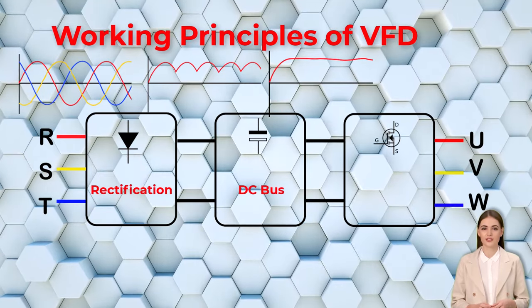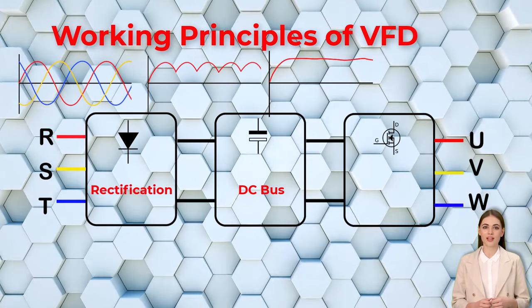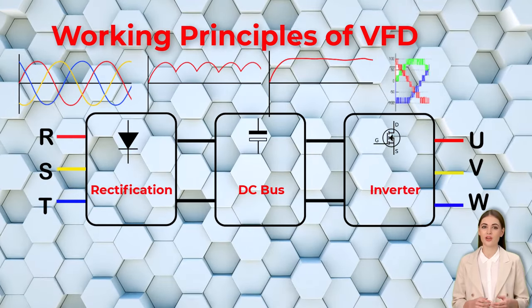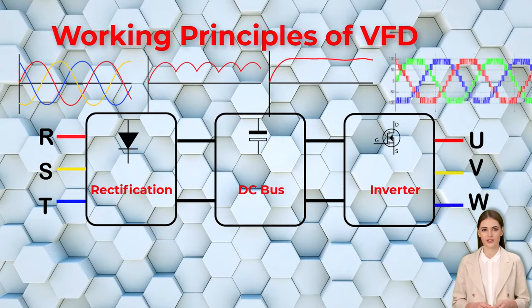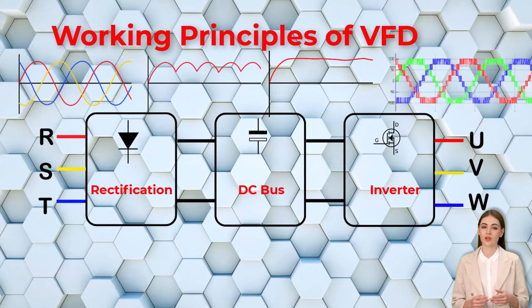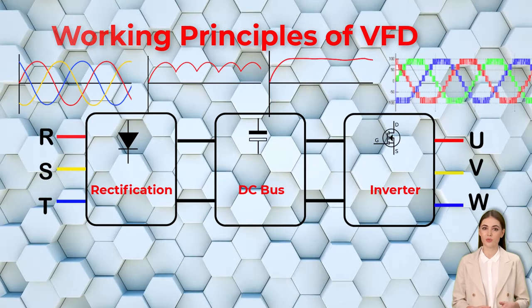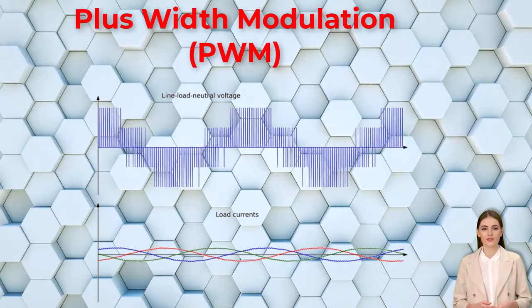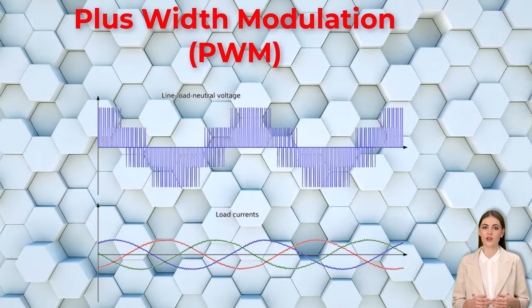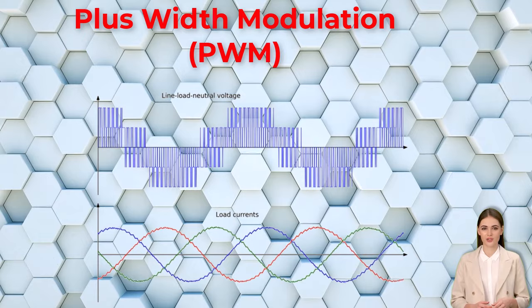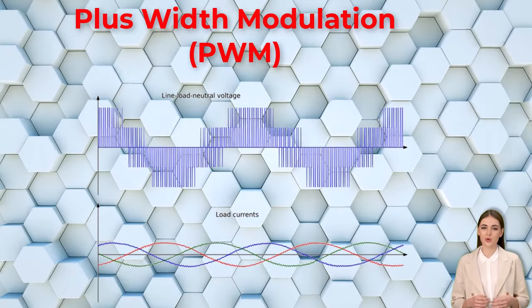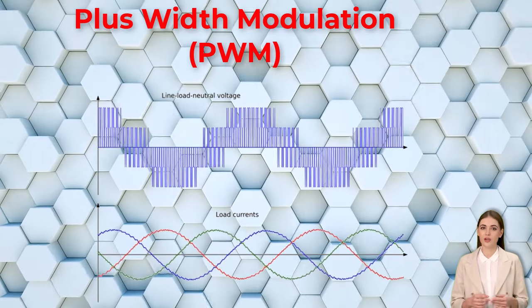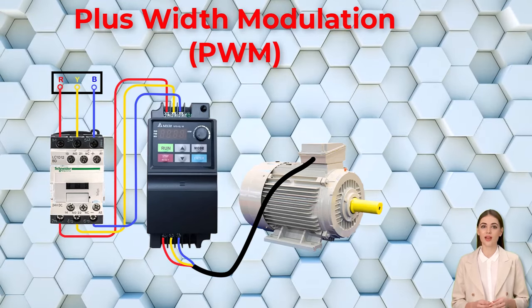The DC bus is a large capacitor that acts as temporary storage for the rectified DC power. The third stage is the inverter: the DC power from the DC bus is converted back into AC power using pulse width modulation (PWM) techniques. The inverter precisely controls the frequency and voltage of the output AC power. PWM works by rapidly switching a transistor on and off, creating a series of pulses that average out to the desired voltage level. The frequency of the pulses determines the output AC frequency, and the average voltage of the pulses determines the output voltage.